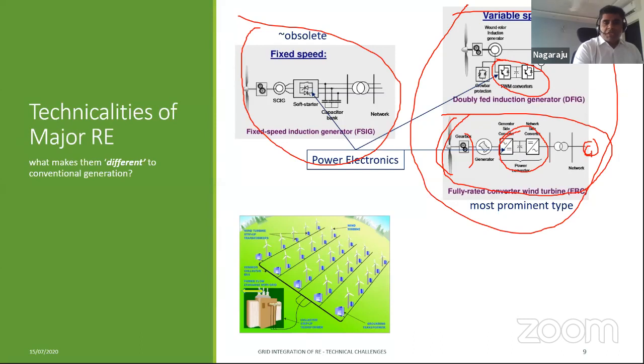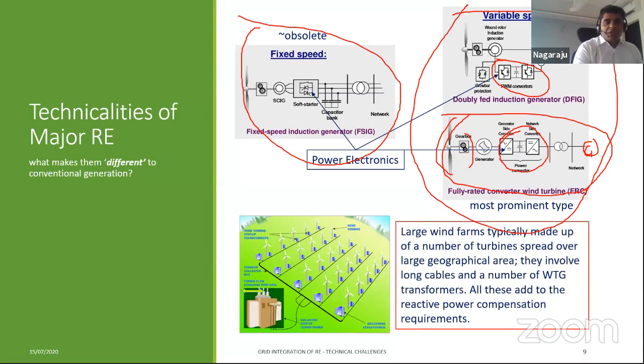Now, what is the importance of this? Large wind farms are typically made up of a number of turbines spread over a large geographical area. They involve long cables and a number of wind turbine transformers. So what are they making? All these are adding up to the reactive power compensation requirements. They themselves are reactive elements, but they are challenging because it's a mix. There are cables and there are transformers. When we talk about inductive side reactive power, the transformers become challenging. And when we talk about capacitive side reactive power, the cables become challenging to compensate for. So we will look at that when I come to the practical applications.